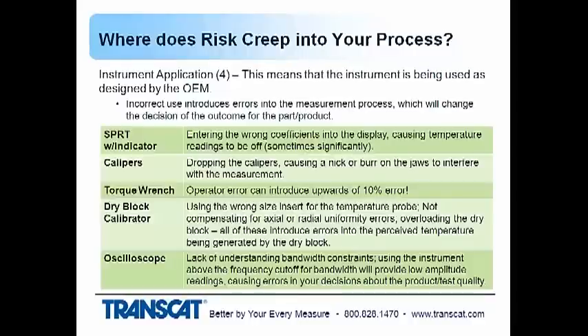A set of calipers. Those are easily picked up and moved around and possibly dropped, and if you have nicks or burrs on the jaws, that's going to shift your zero or possibly affect your readings. Torque wrenches. Without having any damage to the instrument at all in its normal use, there's enough influence from how the operator uses a torque wrench that you can introduce up to 10% error in the reading. And a good gauge repeatability and reproducibility study would indicate how much error you have.